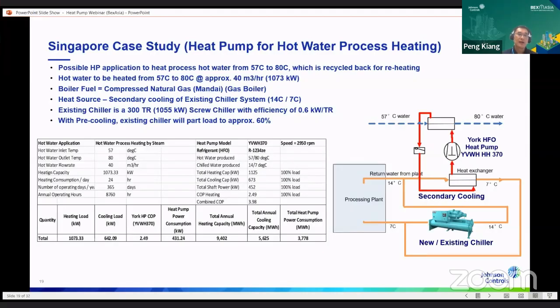And then we have a heat source. In this particular case, we are using a parallel cooling methodology. So this is an existing plant where there's a chiller running about 300 tons of chilled water at the same time. So we are trying to use a heat pump to pre-cool the water at the same amount of temperatures and extract this cooling capacity to generate hot water on the other side at 80 degrees C. So you can imagine that we are putting in a heat pump to do both cooling and heating at the same time to create both synergy of savings.